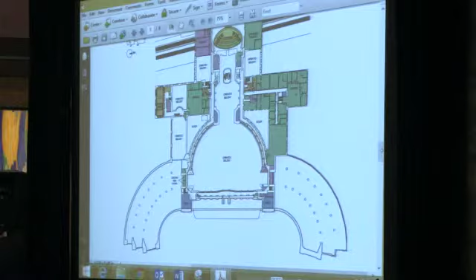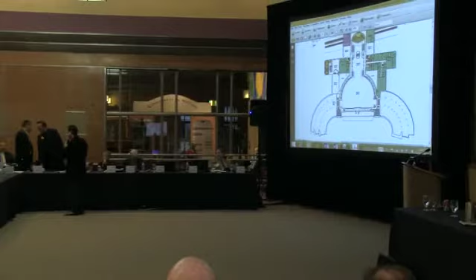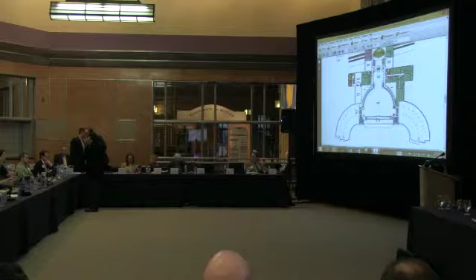The advantages are several. You don't have major runs for your outside air, and you can split north and south without huge runs either — the economy of the sheet metal is going to be tremendous. By not having multiple remote locations, you can also control the size of your units, and if they're in similar locations you can use them for redundancy. Meaning, if I can stack three units and need only two, I have a third for redundancy and spare capacity at peak loads.